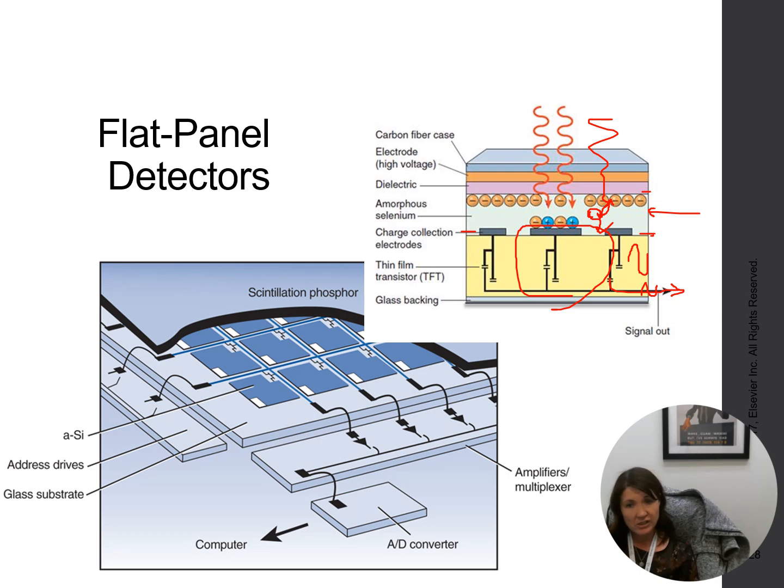This is where I was mentioning today, some of these are being built now where they have their own analog to digital converter right there in the TFT, so that as soon as that signal gets stored in that capacitor, it gets processed in the ADC, and we don't have electrical signals any longer coming out. We have quantized signals coming out where there's an actual value associated, not an electrical charge.